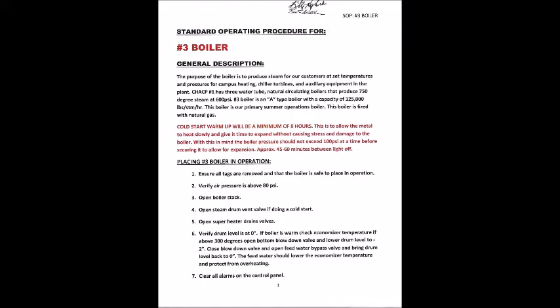Cold start warm-up will be a minimum of 8 hours. This is to allow the metal to heat slowly and give it time to expand without causing stress and damage to the boiler. With this in mind, the boiler pressure should not exceed 100 psi at a time before securing it to allow for expansion, approximately 45 to 60 minutes between light off.